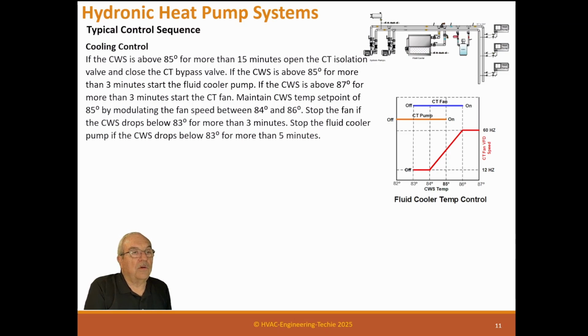Maintain the condenser water supply temperature set point of 85 degrees by modulating the fan speed between 84 and 86. Stop the fan if the condenser water temperature drops below 83 degrees for more than 3 minutes. Stop the fluid cooler pump if the condenser water drops below 83 degrees for more than 5 minutes.